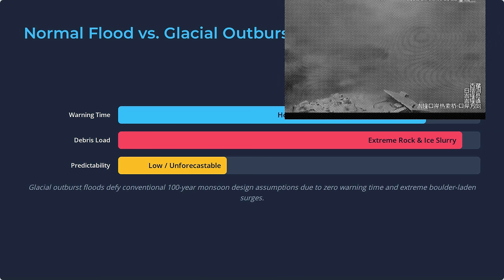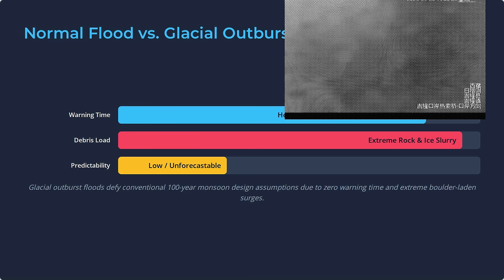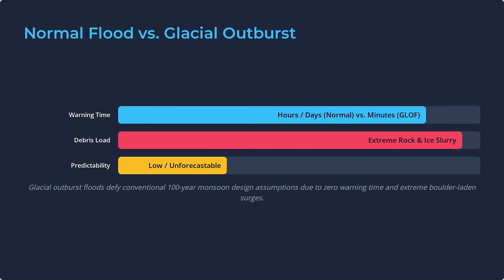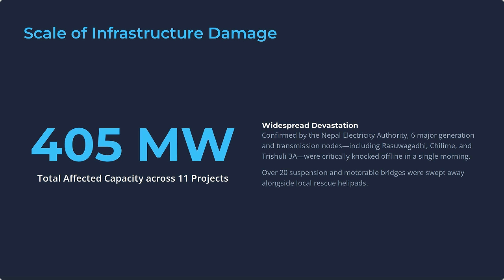Real engineering responses are already being discussed after this event. First, early warning sensors placed much higher upstream, close to the glacial lakes and unstable ice zones, giving even 15 to 20 extra minutes of alert time, which can be the difference between an empty powerhouse and a full one. Second, rethinking where critical electrical equipment like transformers and control rooms are physically placed. Some projects are now elevating or relocating sensitive equipment further from the immediate river bank, even if it costs more in cabling and civil works. Third, regional coordination: since this river starts in Tibet and ends in Nepal, warning systems need to work across the border, not just within one country's monitoring network.